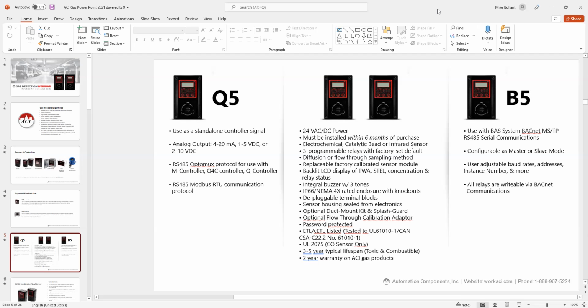Each sensor comes with 3 programmable relays that are all factory set, and a backlit LCD. We also have a buzzer or buzzer horn, 3 different tones on it. You can set internally. The box is NEMA 4X, which is really nice, and everything is password protected. On the BACnet, our BACnet sensors are MSTP, and configurable as master, slave mode, however you decide to do it. It also has different baud rates depending on what control system you're going to be landing the communication bus on. What's the default for the baud rate, 38.4? I believe that is, yeah, 38.4. Yes.